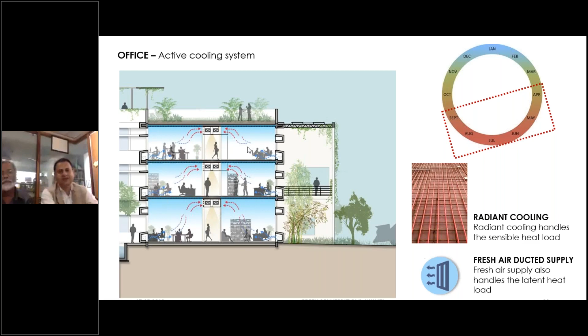So we are taking the double benefit of the return of the water. The chilled water supplied to the whole system averages higher than 6C or 7C. The chilled water running through the radiant piping is above 14C, while in the AHUs it's conventional because the air has to be dehumidified.